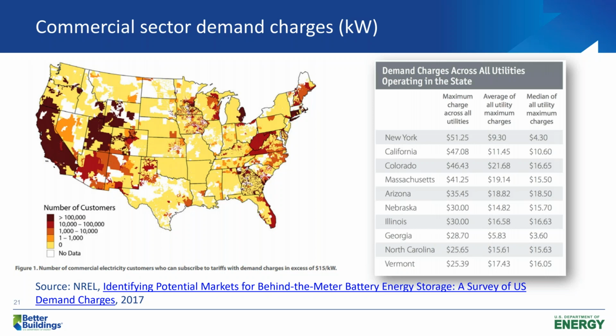High demand charges support battery cost effectiveness. You may want a rate structure with high demand charges, which sounds counterintuitive, but if you're able to manage that demand, those rate structures have lower energy charges, so you can come out ahead financially. More storage projects are economical at the $15 per kilowatt demand charge range. This NREL report from 2017 shows which territories had demand charges in that range across the country.